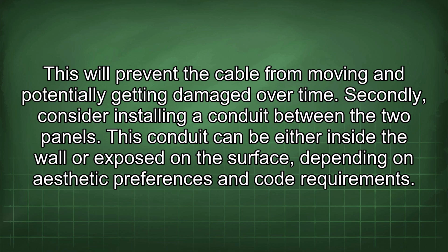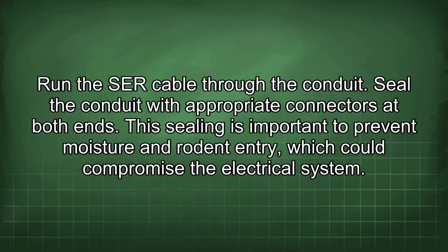Secondly, consider installing a conduit between the two panels. This conduit can be either inside the wall or exposed on the surface, depending on aesthetic preferences and code requirements. Run the SER cable through the conduit. Seal the conduit with appropriate connectors at both ends. This sealing is important to prevent moisture and rodent entry, which could compromise the electrical system.